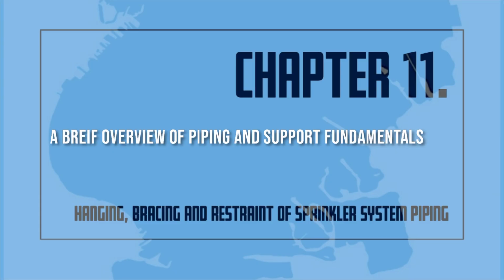A partial list of specific hanger spacing requirements. Standard wall steel pipe with diameters 1 inch and 1 1/4 inch are required to have hangers placed at a maximum of 12 feet apart. For all other pipe diameters, the maximum distance between hangers is 15 feet. The maximum hanger spacing for threaded light wall steel pipe shall not exceed 12 feet apart. The maximum hanger spacing for CPVC, plastic pipe, varies from a maximum 5 feet 6 inches for 3/4 inch piping to a maximum 10 feet on center for 3 inch piping.